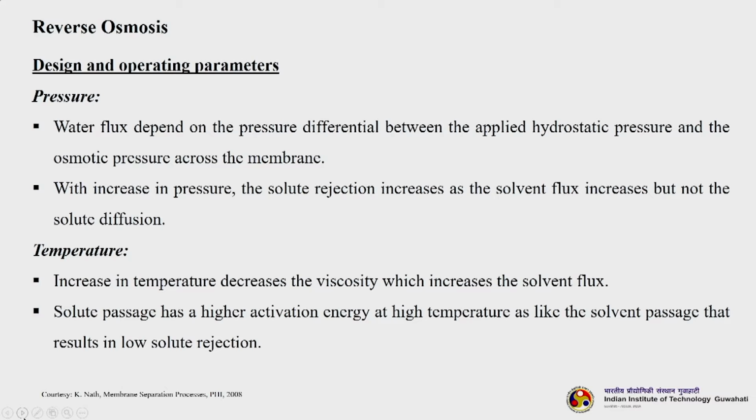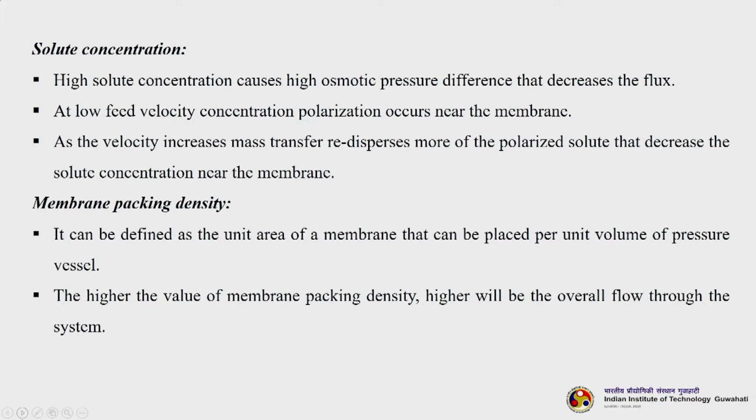Next is temperature. Increase in temperature decreases the viscosity, which eventually increases the solvent flux. Solute passage has a higher activation energy at high temperature, like the solvent passage, that results in low solute rejection. Apart from pressure and temperature, other parameters which affect the performance of RO are solute concentration. High solute concentration causes high osmotic pressure difference that decreases the flux.